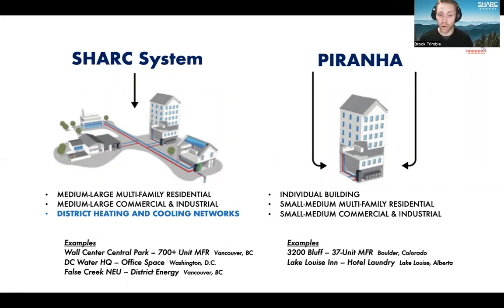A perfect example for office space is the DC Water headquarters in Washington, DC. This is using a SHARC for both heating and cooling of their office space. And finally, looking at the largest types of systems, district heating and cooling networks, a system example is the False Creek Neighborhood Energy Utility, a district heating network in Vancouver, BC. When we look at the smaller options, the Piranha is really well designed for individual buildings. By this, we typically mean small to medium multifamily residential. A great example is the 37 unit multifamily project in Boulder, Colorado, called 3200 Bluff, as well as small to medium commercial and industrial projects like a hotel laundry up in the Rocky Mountains of Canada, the Lake Louise Inn in Alberta. And last slide, please.